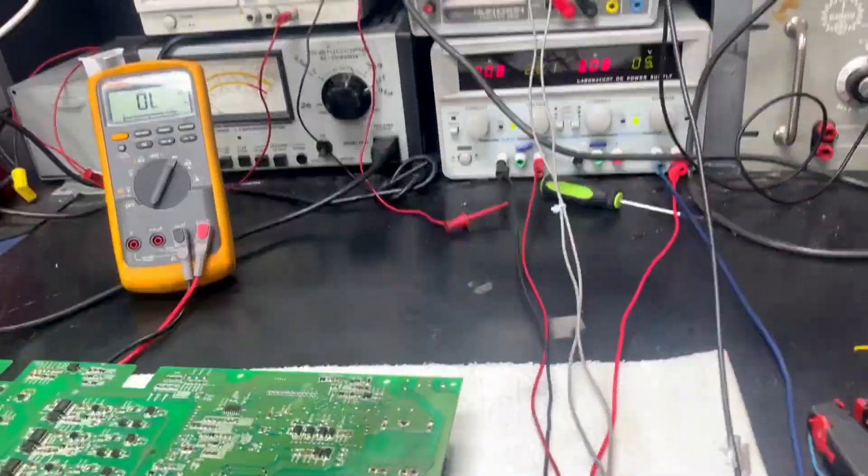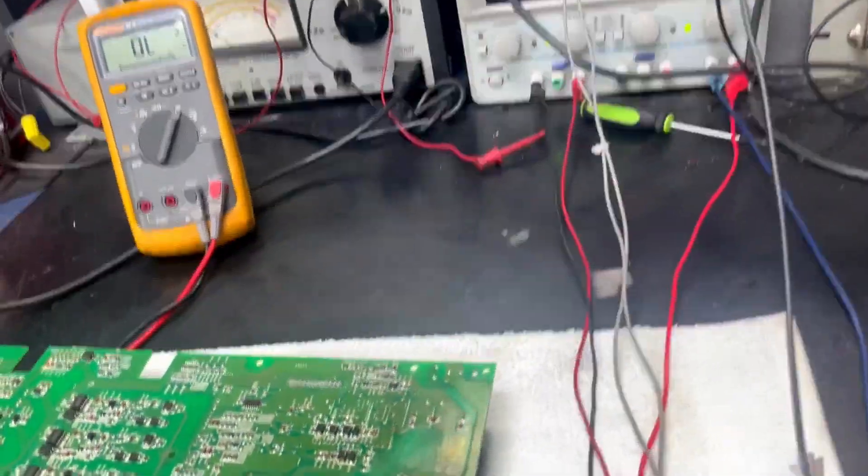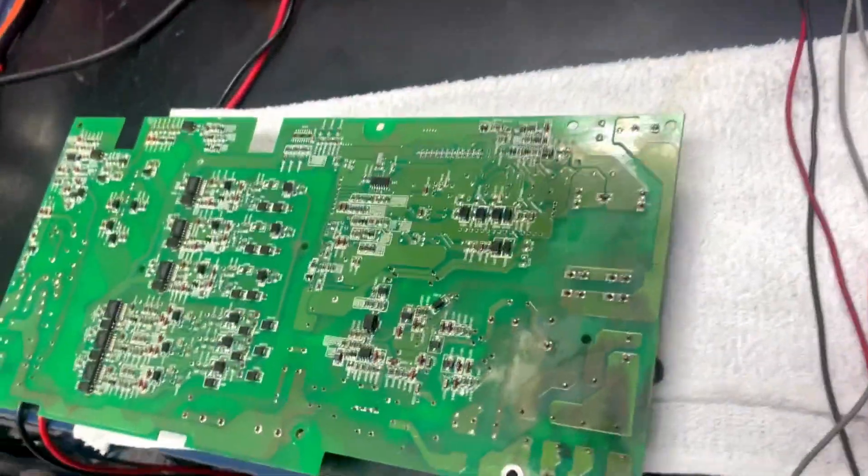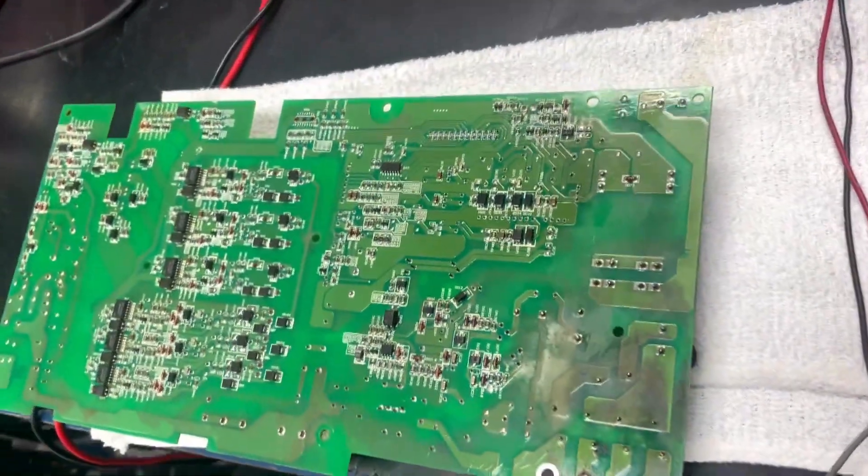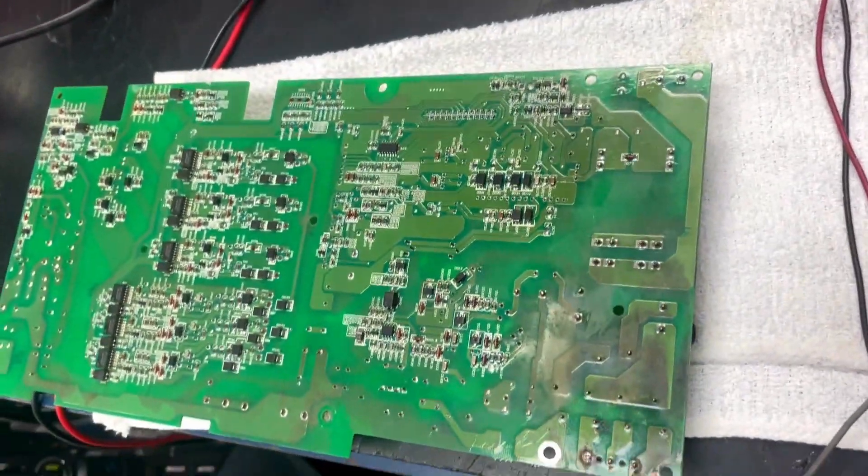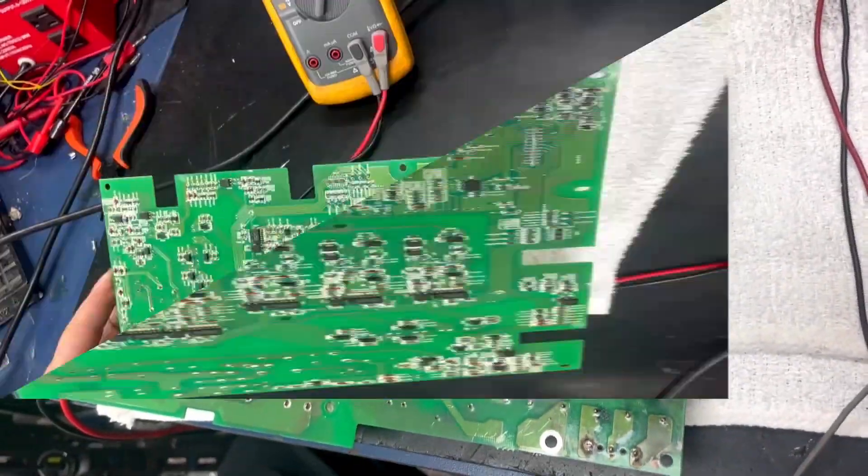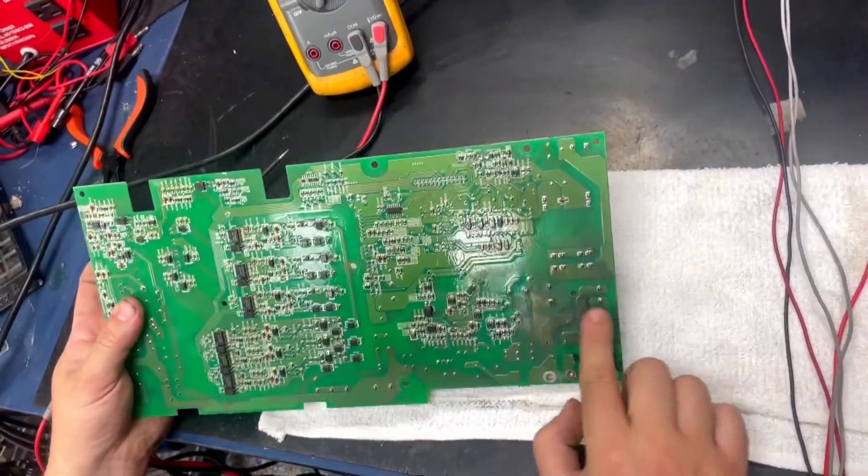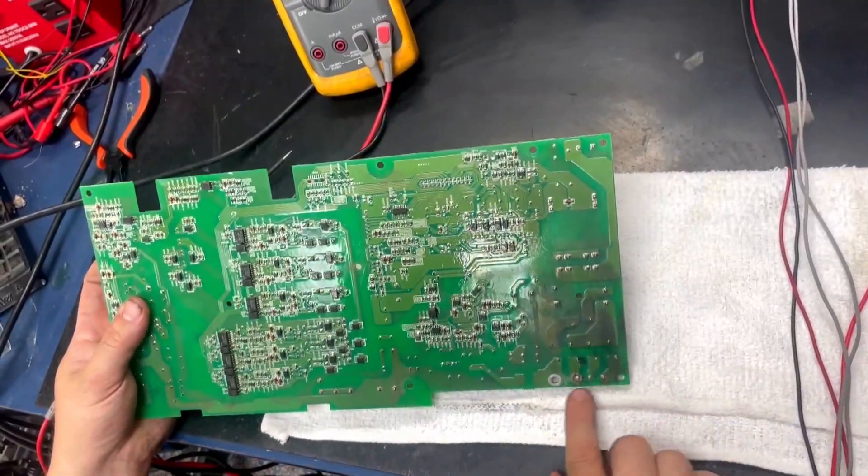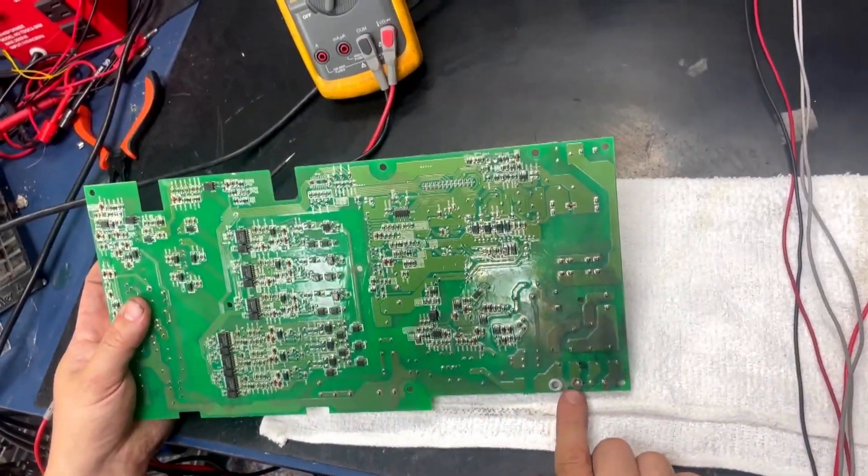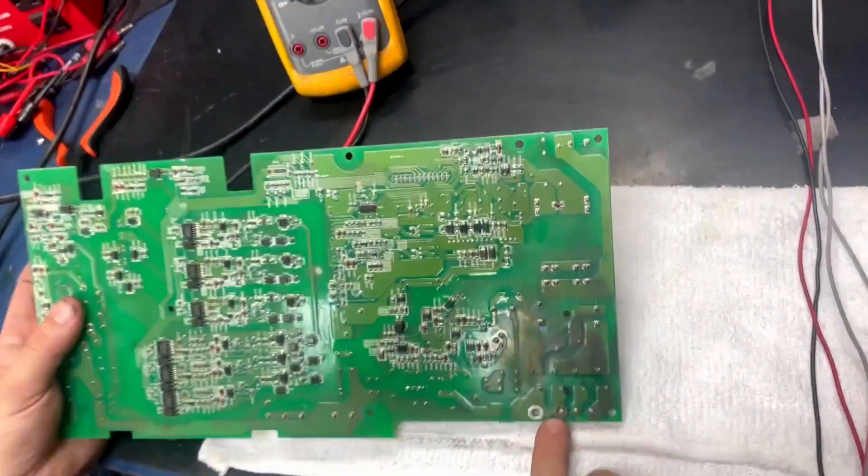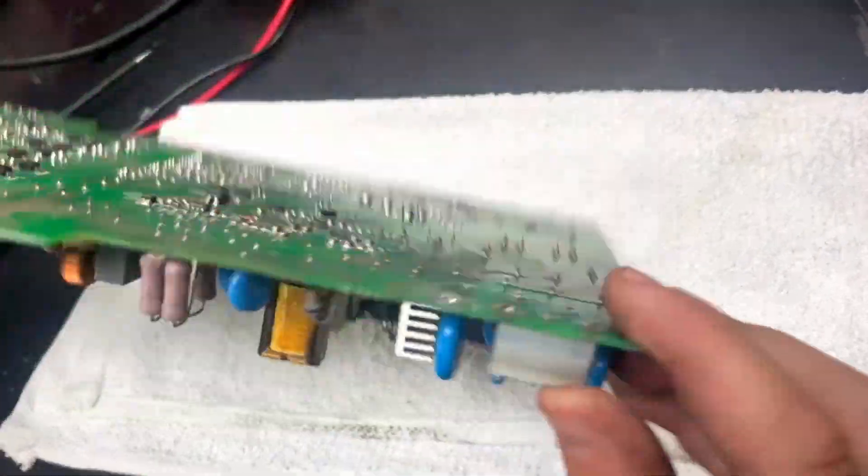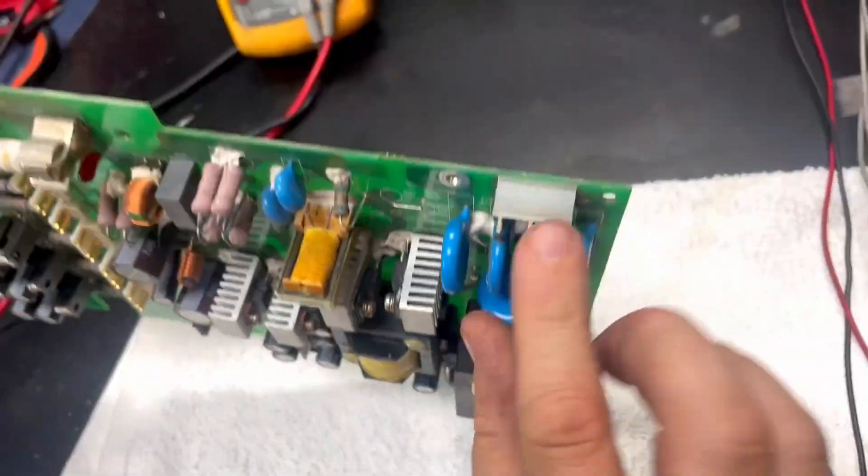Here we have a trigger board, also known as a power drive board, for a PowerFlex 400 Allen-Bradley VFD. On the bottom here, you can see that there was some electrical damage, specifically on these input power pins.